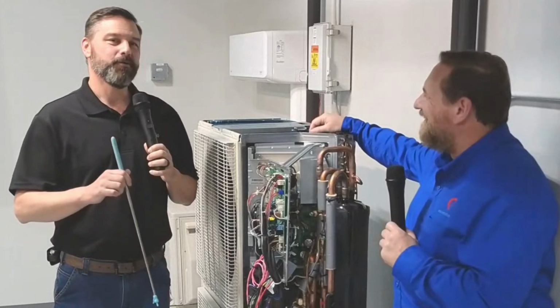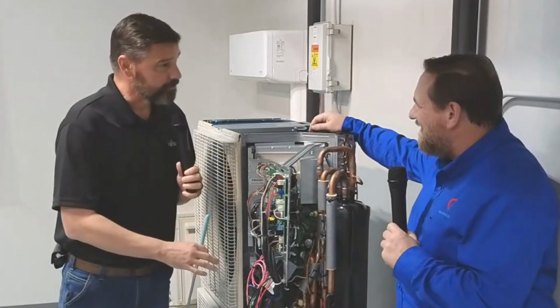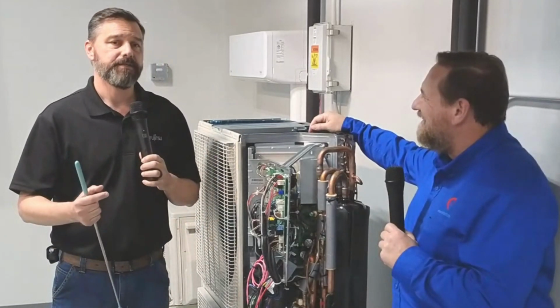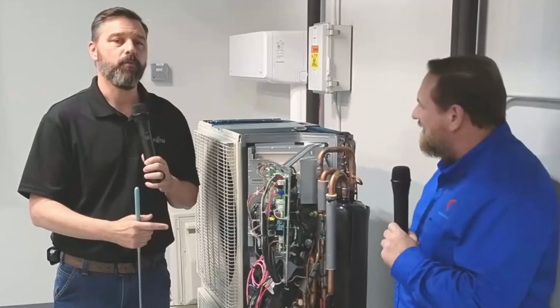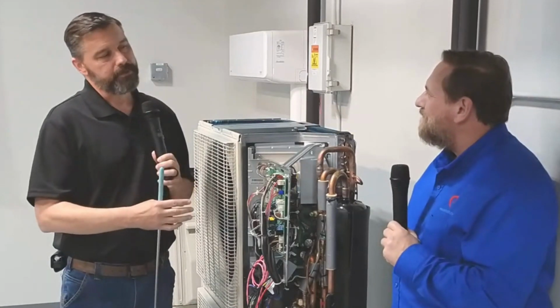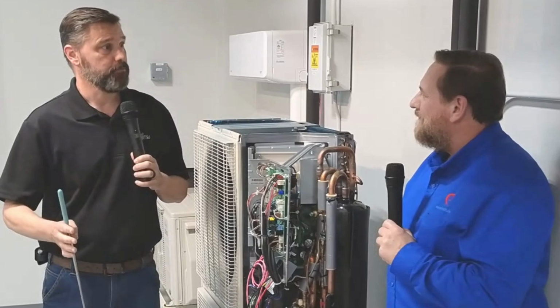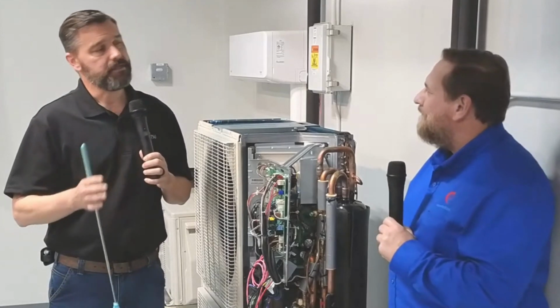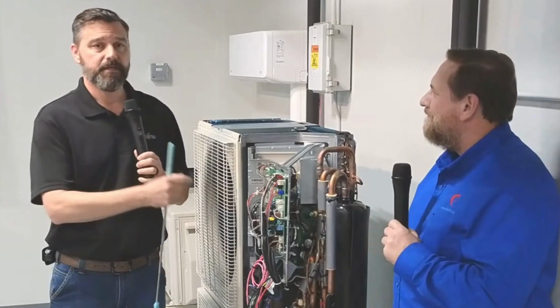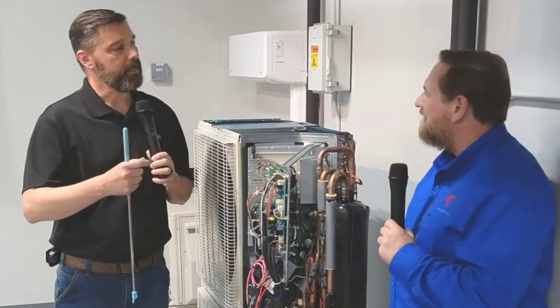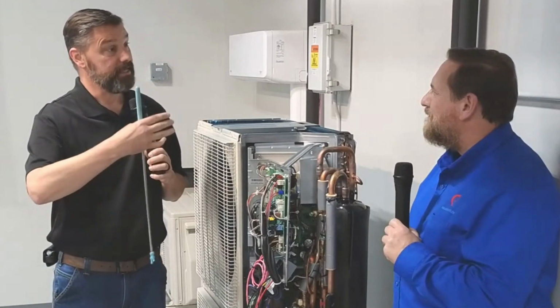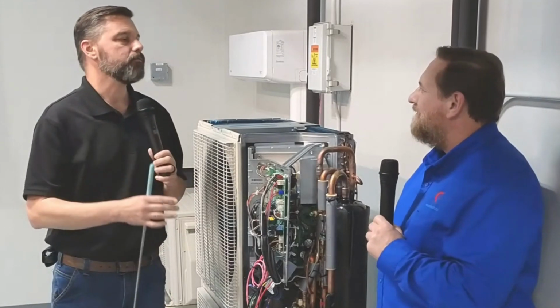Excellent. One of the nice things about the thermistors is when we take the service class, we actually talk about what thermistor controls what, and it tells you at what temperature we're going to begin to enter that protection mode. So we can begin to understand what the system's doing based on the temperature of that thermistor. And so each protection code has an engage at what temperature, and then it has a release.